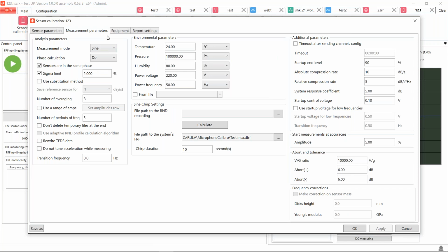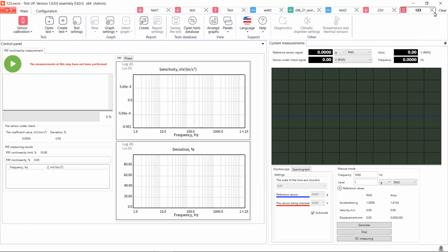So let's pretend that we have filled in all the parameters and we can save the settings for calibration in sine measurement mode. Let's press OK. Here I would like to draw your attention to the manual mode at the bottom. It is applied to generate a certain frequency at a certain level. Now let's open Test Settings again.